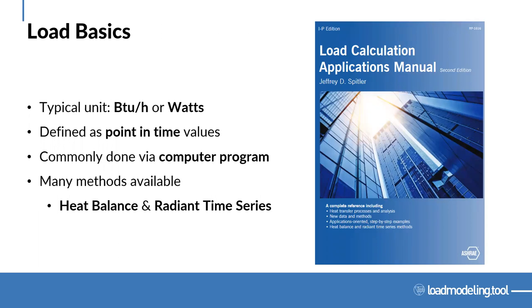Some quick load basics. First, typical units: if we're in IP, we're talking BTU/h; if we're in SI, we're talking watts. So if I have 12,000 BTU/h in my room, that's the load I need to counteract. When we're talking a load model, we're talking a point in time — the specific time that load occurs. We're not looking at yearly results; that's more on the energy side. We're really talking about the exact time this happens, which is going to be the worst-case load for my project.